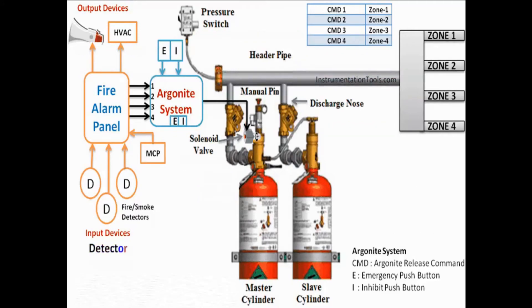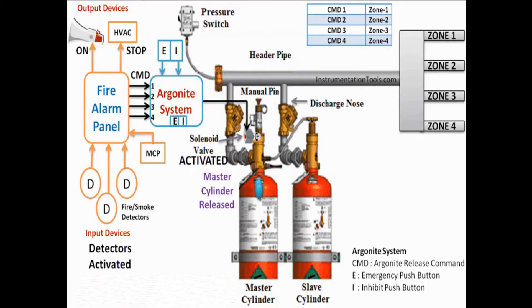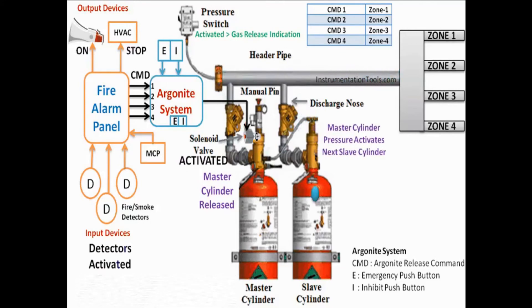As discussed, we have four zones or areas, so we must release the gas to the fire-affected zone only. An on/off valve will be provided in the zone 1, zone 2, zone 3, and zone 4 discharge pipelines (not shown in animation). Whenever we receive a command from the fire alarm panel, the respective zone on/off valve will be opened immediately while the remaining valves stay closed. So if command 4 is received, then the zone 4 valve will be activated.